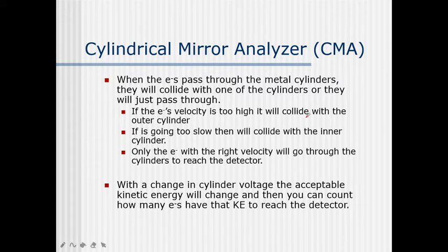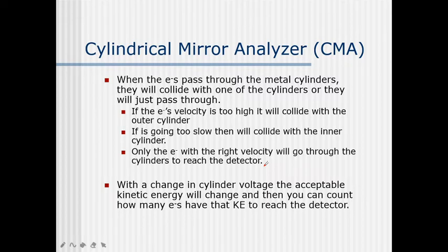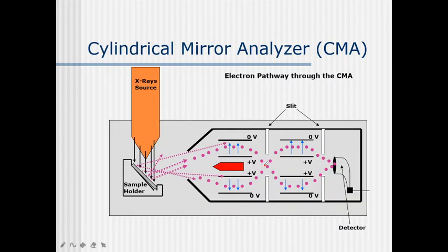If an electron's velocity is too high it will collide with the outer cylinder; if too slow, it will collide with the inner cylinder. Only electrons with the right velocity will pass through the cylinders to reach the detector. Only electrons that reach the detector give the spectra. With a change in the cylindrical voltage, the acceptable kinetic energy changes, and we can count how many electrons have the kinetic energy to reach the detector. This is how the cylindrical mirror analyzer works.